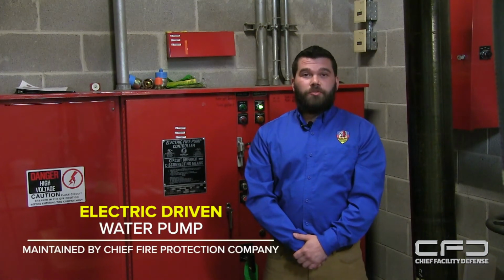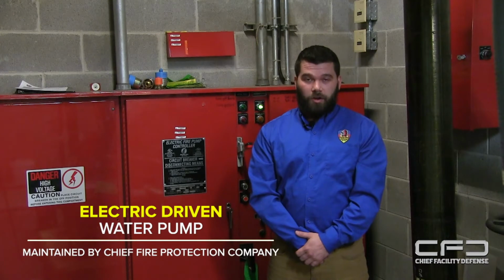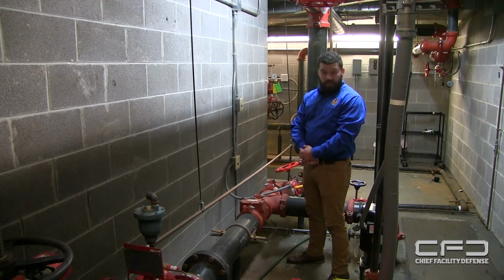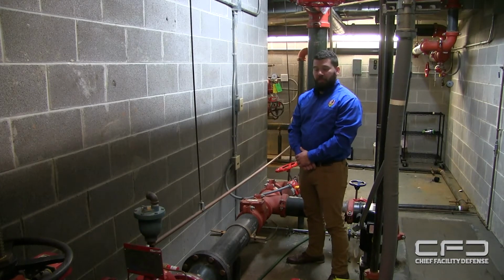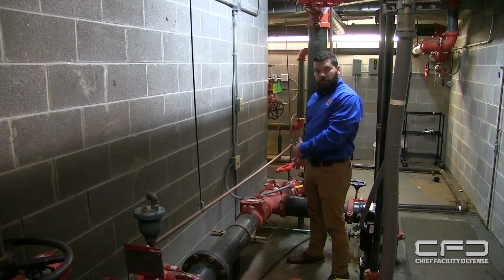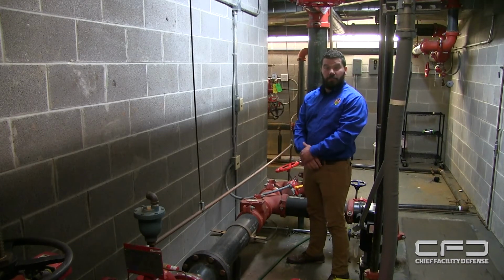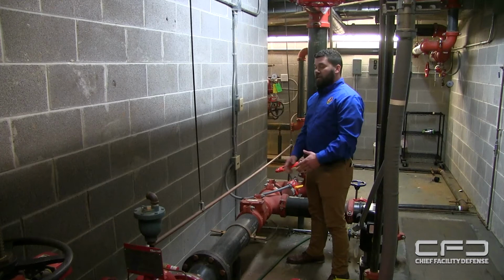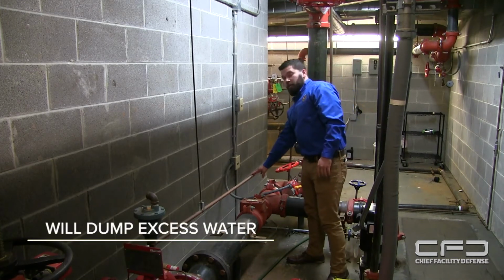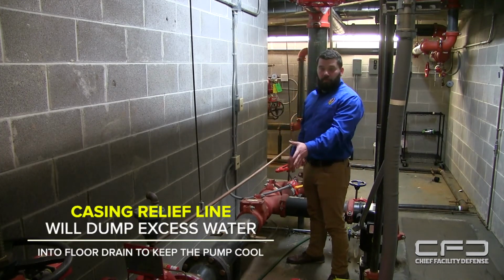Your building utilizes an electrically driven fire pump due to lack of either volume or pressure from the city water supply, and is currently maintained by Chief Fire Protection, located down here in the basement room of your building. In the event that the fire pump is ever running, go to the alarm panel, see where the alarm is coming in at, check the floor, make sure there is no fire, no emergency. And if the water is dumping out onto the floor in a no-flow situation, if there's not a sprinkler head that's going off or a pipe that has burst, the casing relief line will dump the excess water into the floor drain to keep the pump cool.